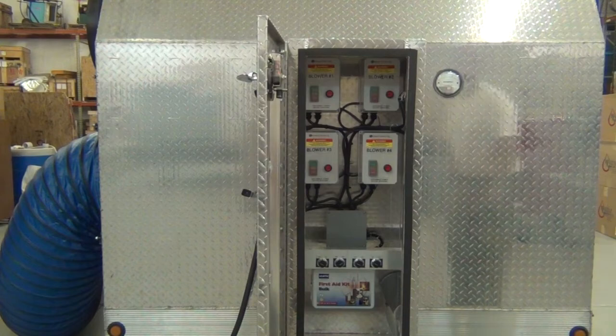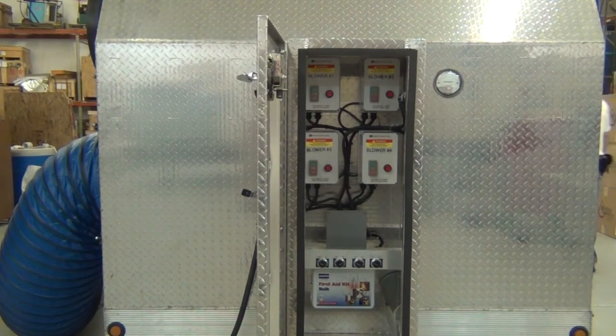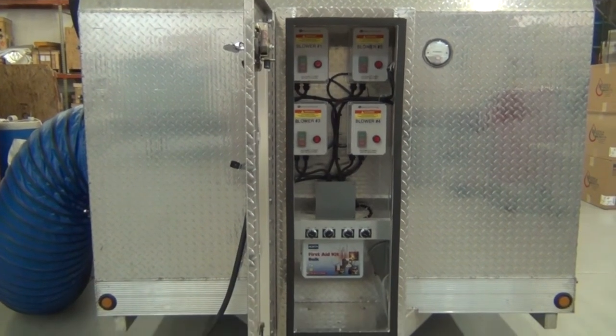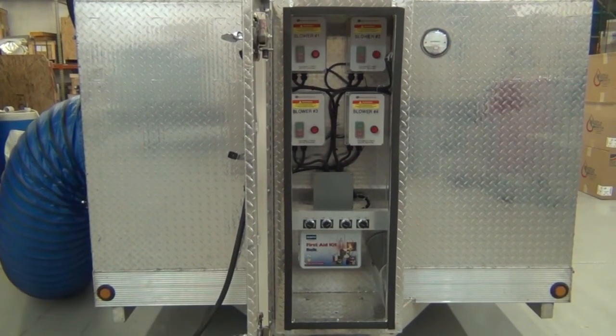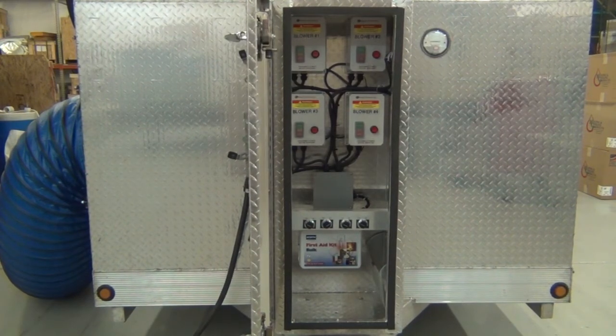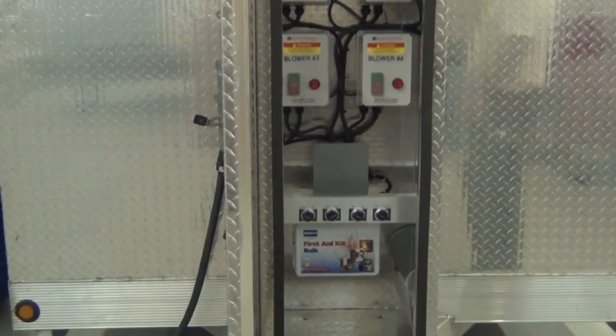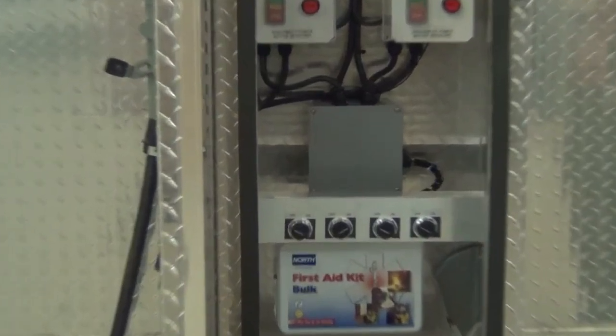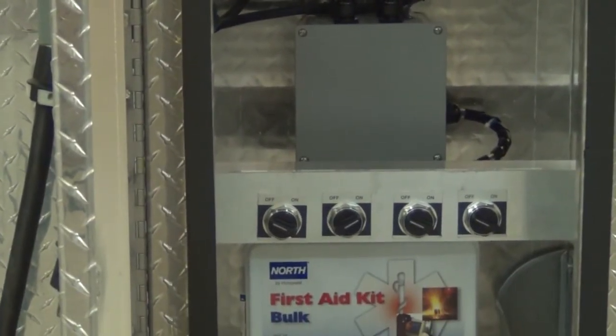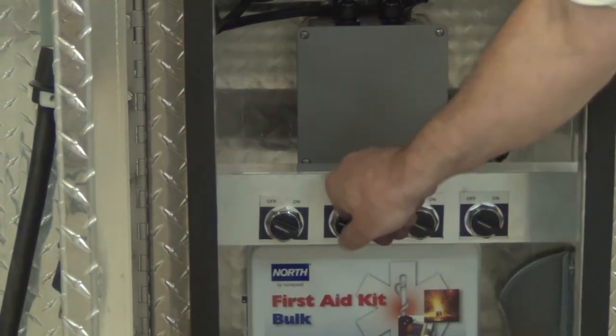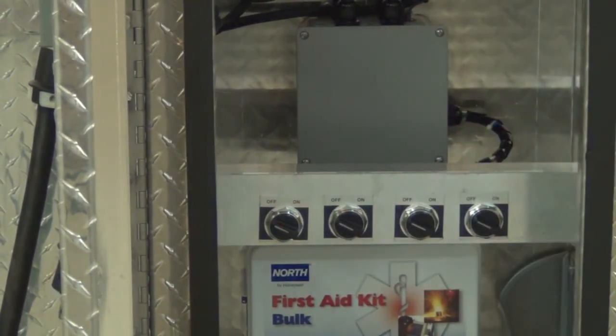When you shut the unit down or you want to idle the system for filter changes or filter maintenance, you should always shut the switch off first and allow the motor to spool down. The variable frequency drive does have a circuit in it to actually slow down the blower at a controlled rate so the variable frequency drive system does not have a voltage overload. So when we turn the fan off, we turn it to off in this location and allow the fan to slow down and eventually stop, which should take about 32 to 35 seconds.